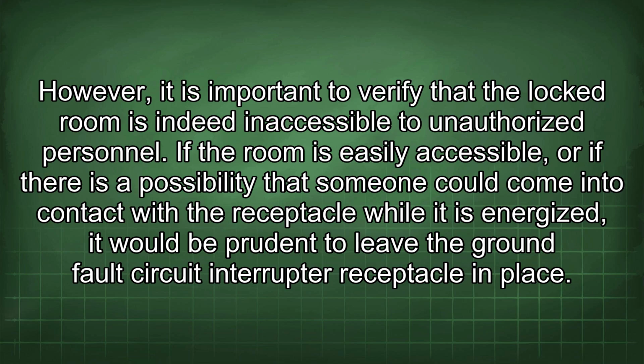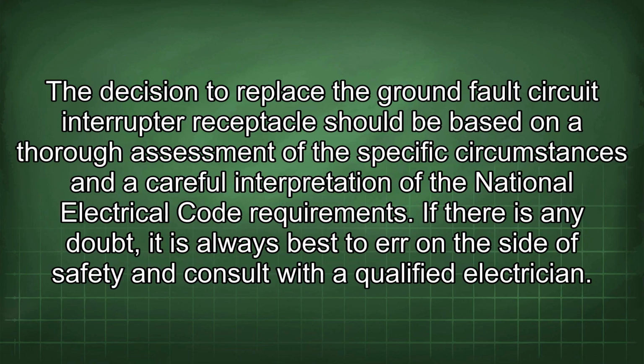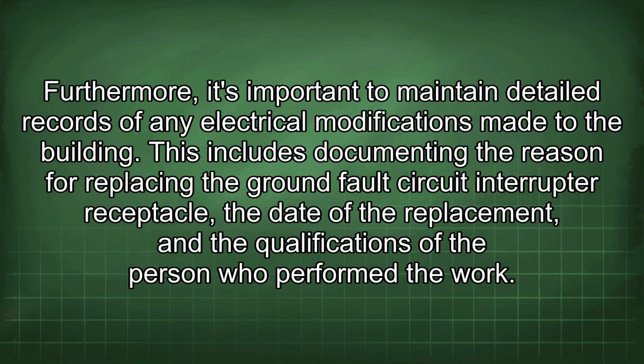If the room is easily accessible, or if there is a possibility that someone could come into contact with the receptacle while it is energized, it would be prudent to leave the ground fault circuit interrupter receptacle in place. The decision to replace the ground fault circuit interrupter receptacle should be based on a thorough assessment of the specific circumstances and a careful interpretation of the National Electrical Code requirements. If there is any doubt, it is always best to err on the side of safety and consult with a qualified electrician. Furthermore, it's important to maintain detailed records of any electrical modifications made to the building.